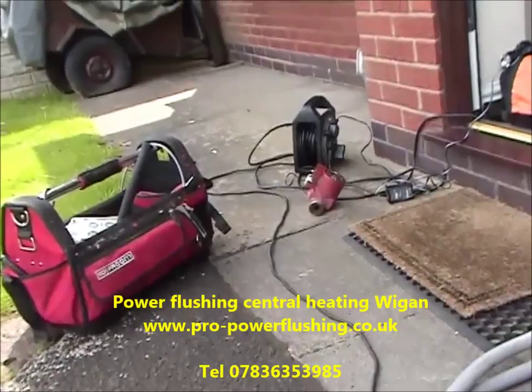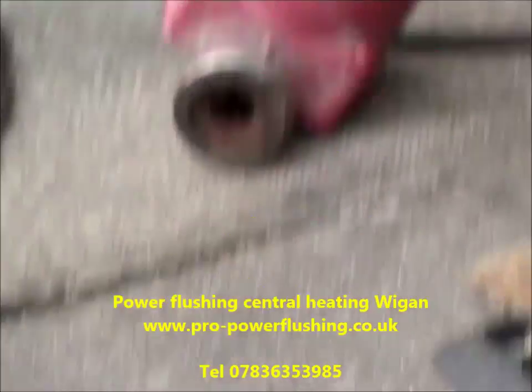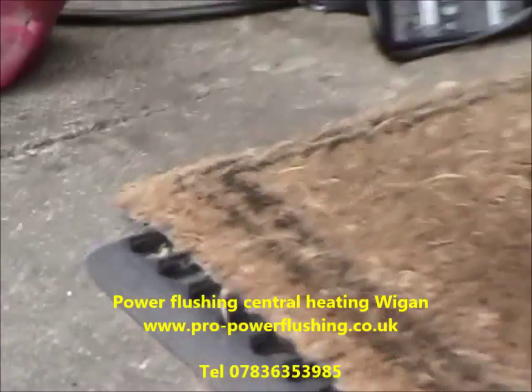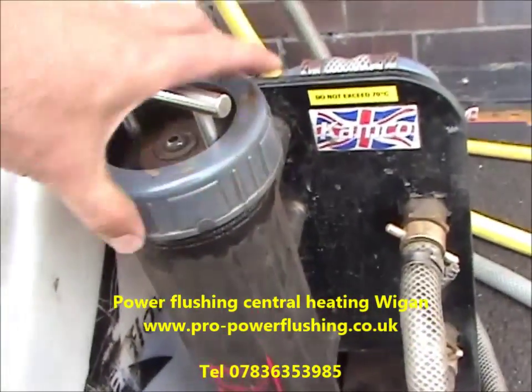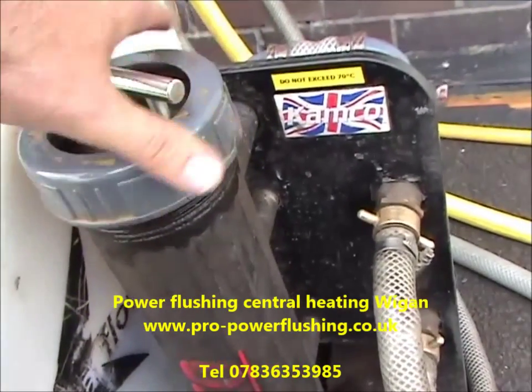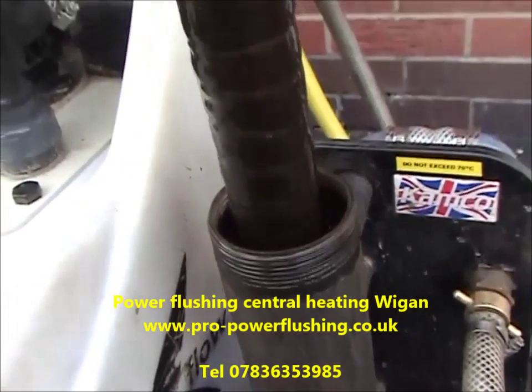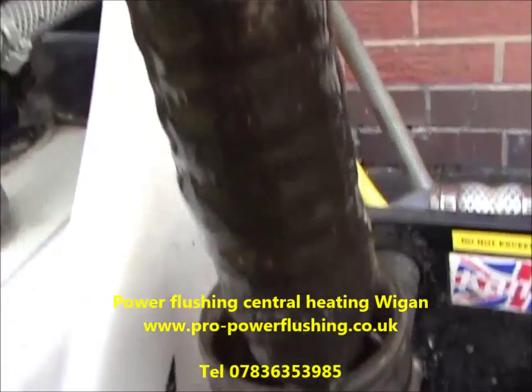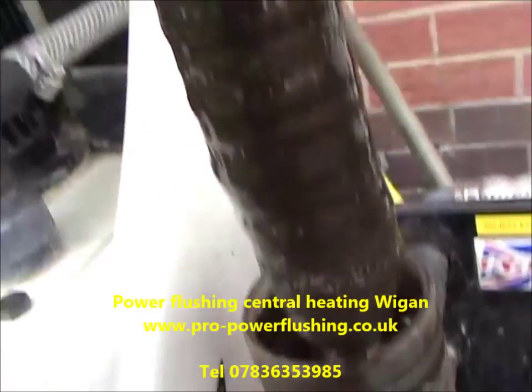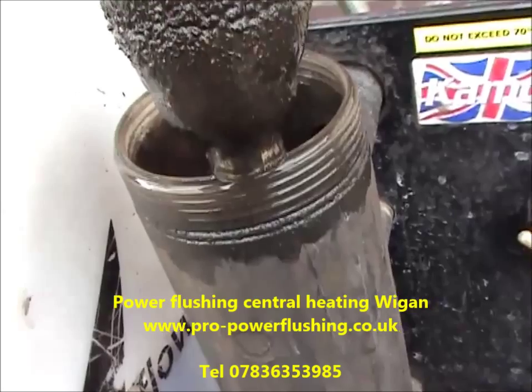Plus we've taken the pump off, which is over there, you can see that, and now it's got some rust and corrosion inside it as well. So we'll just get back to this magnet, let's have a look at it. Oh yeah, wow, unbelievable, look at that. Now I must admit, even I'm surprised by the amount of rust and corrosion and sludge that's on this magnet in this central heating system.